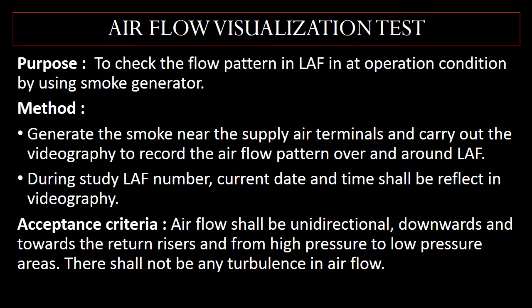The acceptance criteria of the air flow visualization test is that air flow shall be unidirectional, downwards and towards the return risers, and from high pressure to low pressure areas. There shall not be any turbulence in the air flow.